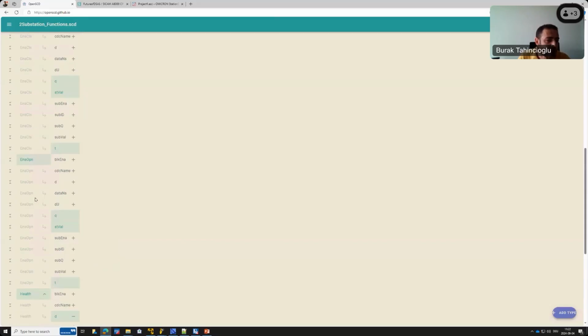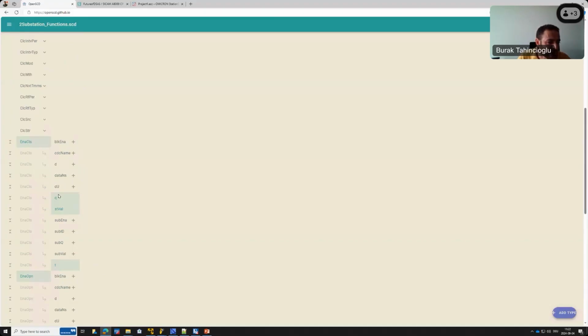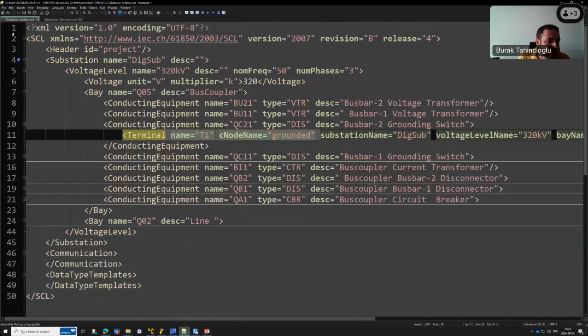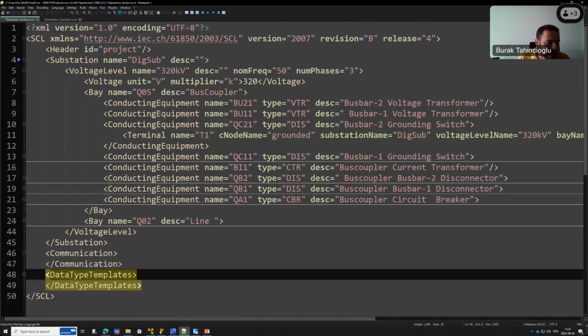Normally, how does a CILO look? It has enable-open and enable-close, and each data object would have the status value Q and T — the same for both enable-open and enable-close. Whenever I click 'add type', I get my very first logical node in my IED. At this point we're starting to build the section called data type templates. Based on the data type templates, the IED will instantiate the logical nodes.